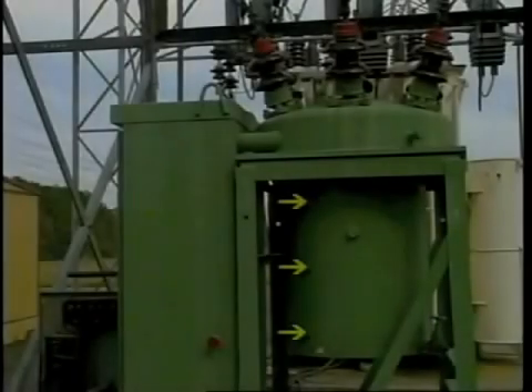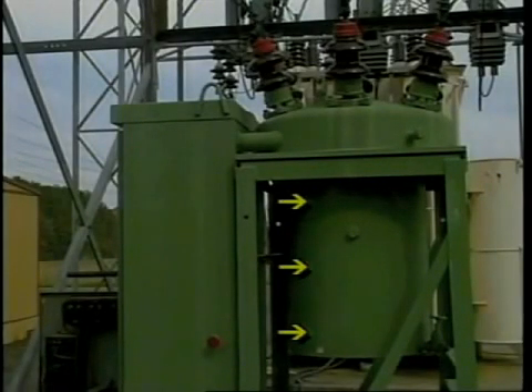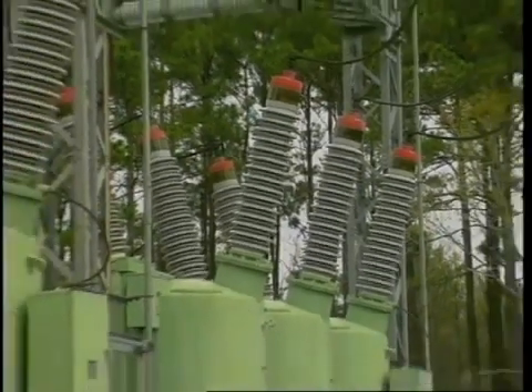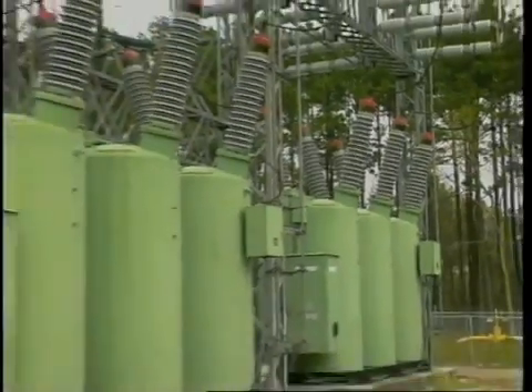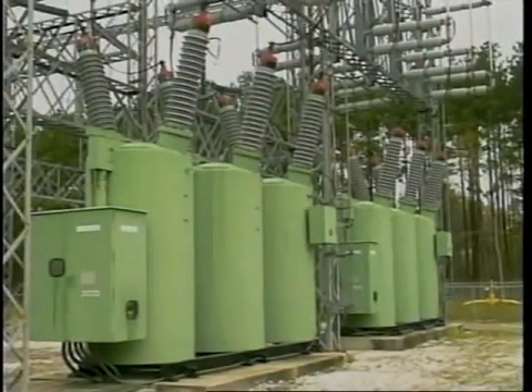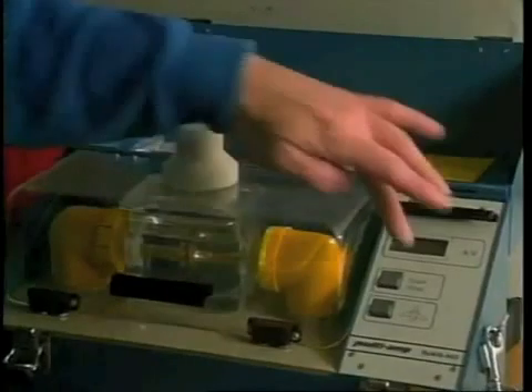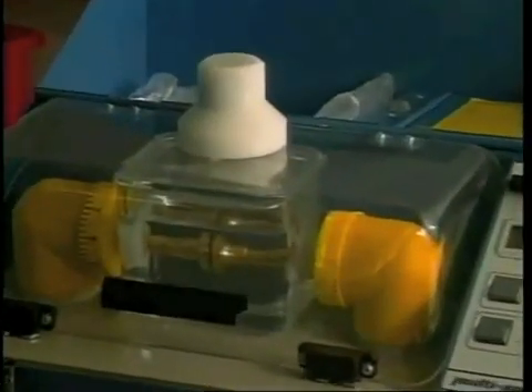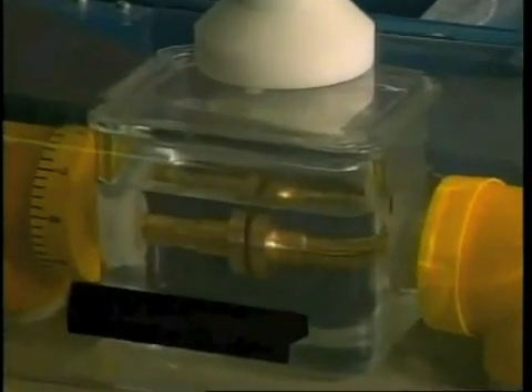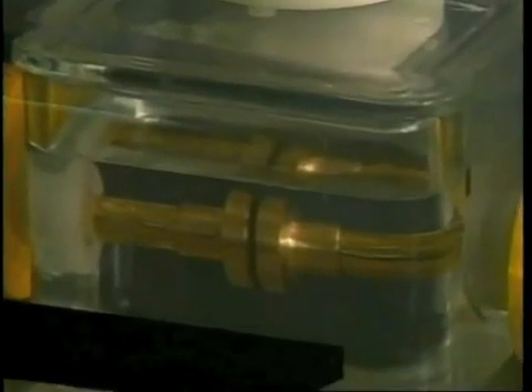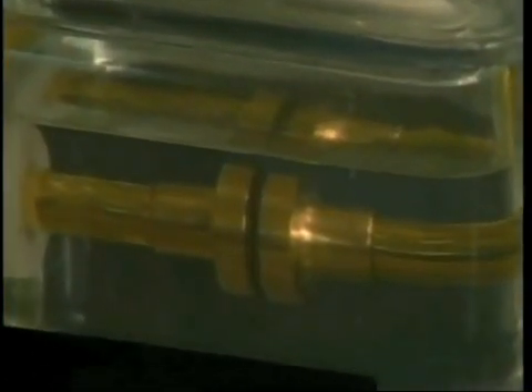The oil tank on oil-filled circuit breakers holds the insulating fluid that provides the insulating and interrupting medium. The voltage level and interrupting capacity determine the volume of oil and the number of tanks that are used. The oil must be free of contaminants and have high dielectric strength. Special electrical tests are used to determine the oil's suitability.